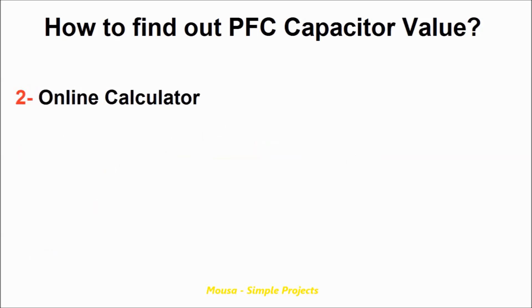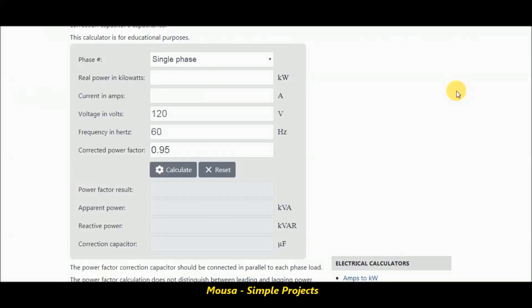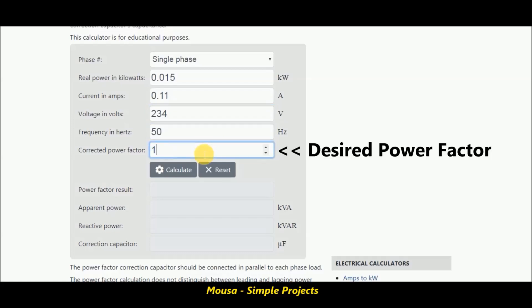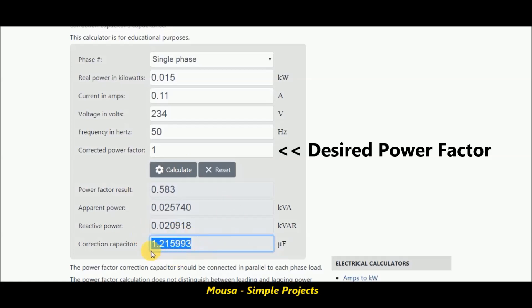The second way to find out the capacitor value for power factor correction is by using online calculators. You can find the link to this calculator below in the description. You have to insert the power of your load in kilowatts, and also insert the voltage, current, and power factor. As you can see, the capacitor value comes out to 1.2 microfarads, which is the same as I calculated before.